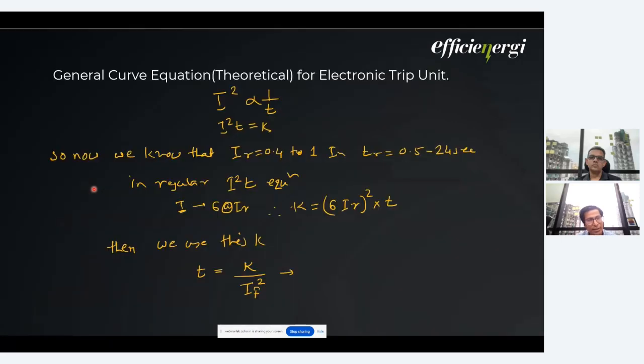We'll move to the next slide. Okay, so there is a general curve equation, a theoretical curve equation for electronic trip units. We basically know that I squared is inversely proportional to the time. This gives us the equation I squared T is equal to a constant. Now, how is this equation used to draw the curve? I'll be explaining that in the next slide, but here we know that for IR, the settings start from 0.4 and go up to 100% of the nominal current, and then we have TR, which usually starts from 0.5 seconds and goes up to 24 seconds.